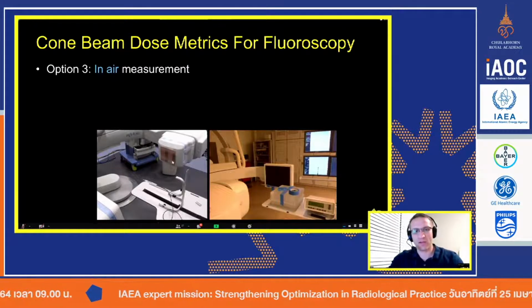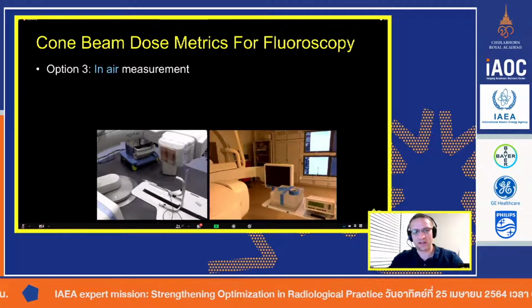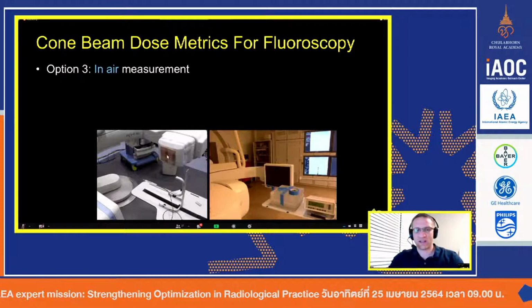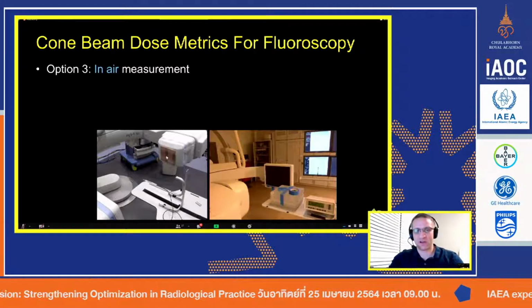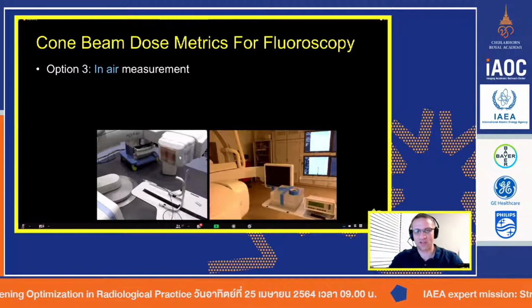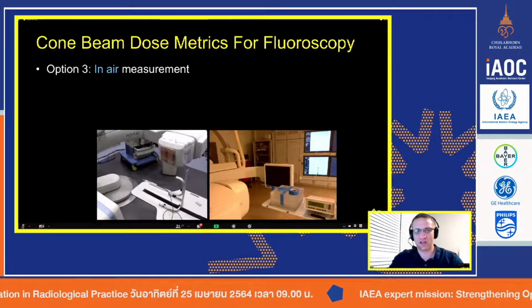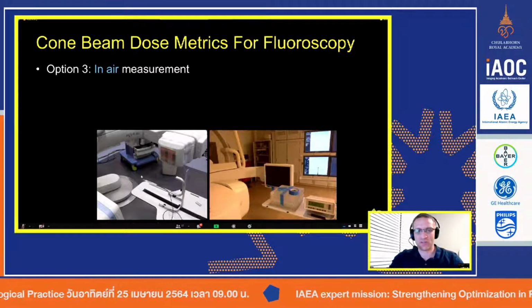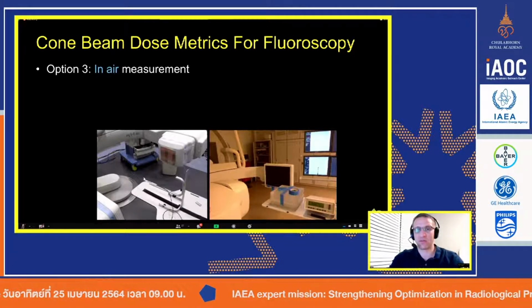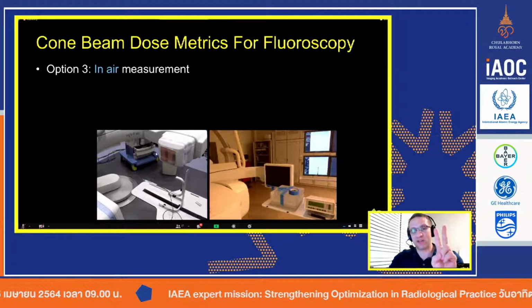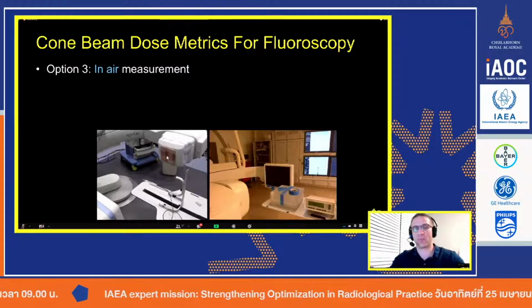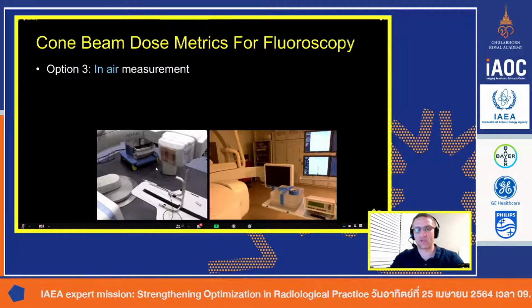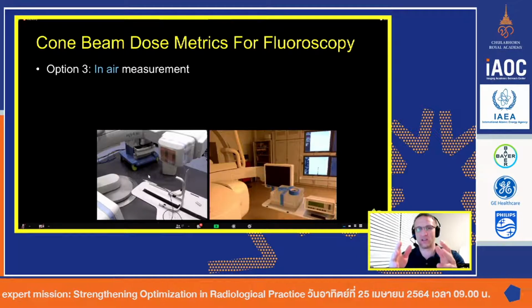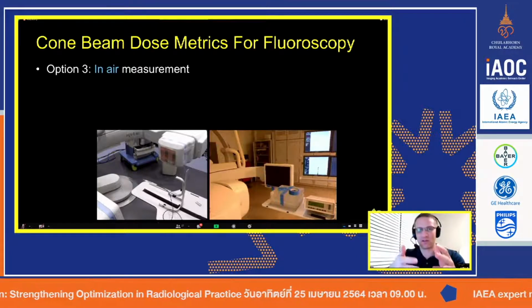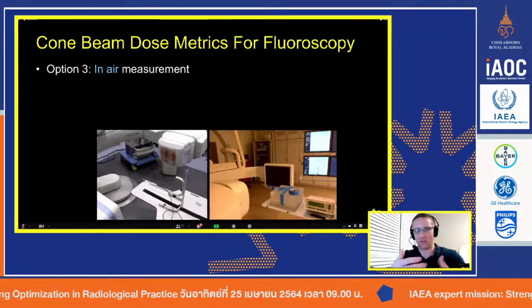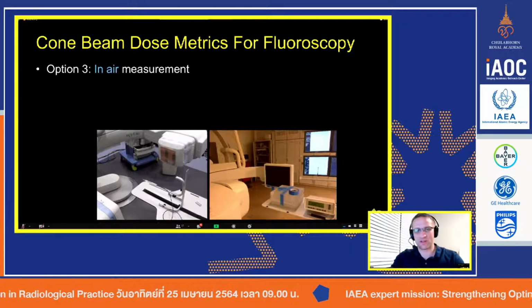I put my filters on the detector. Like I said, if you put the filters on the X-ray side, on the source side, you reduce the amount of radiation by the time it gets to your ion chamber. The second thing that happens is you actually do create scatter coming off the copper. You will get scatter coming off this. So you have the potential to change the measurement every time, because the scatter is going to be different every time you make a measurement.